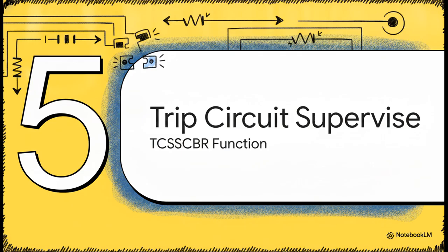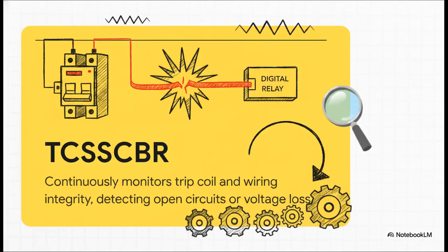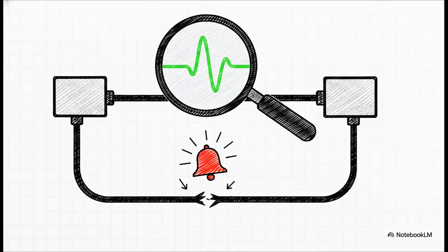And our final piece, Section 5, Supervising the Trip Circuit Breaker, TCSSCBR. So we've covered the mechanical side, but what about the electrical pathway? Introducing TCSSCBR, or Trip Circuit Supervision. This function continuously monitors the integrity of the trip coil and all its associated wiring. Because think about this terrifying blind spot. You could have a perfectly healthy, well-lubricated mechanical breaker and a brilliant digital relay, but if the single copper control wire connecting the two is broken, that breaker is completely useless when a fault occurs. TCSSCBR works tirelessly behind the scenes to prevent exactly that.